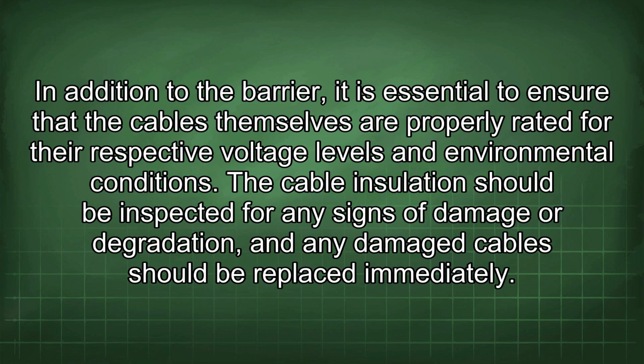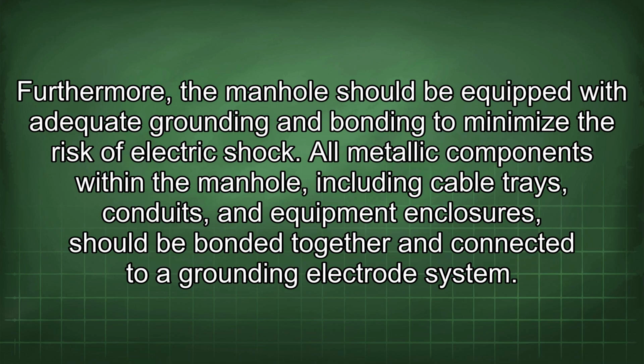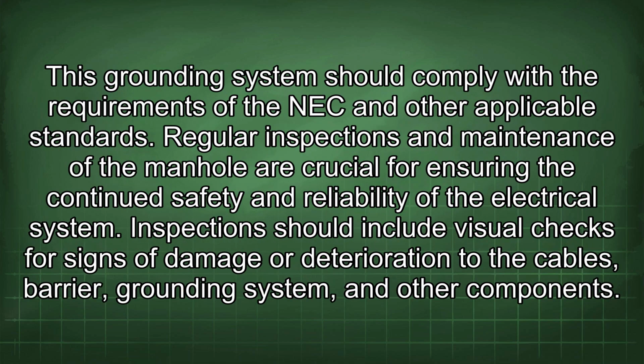In addition to the barrier, it is essential to ensure that the cables themselves are properly rated for their respective voltage levels and environmental conditions. The cable insulation should be inspected for any signs of damage or degradation, and any damaged cable should be replaced immediately. Furthermore, the manhole should be equipped with adequate grounding and bonding to minimize the risk of electric shock. All metallic components within the manhole, including cable trays, conduits, and equipment enclosures, should be bonded together and connected to a grounding electrode system. This grounding system should comply with the requirements of the NEC and other applicable standards. Regular inspections and maintenance of the manhole are crucial for ensuring the continued safety and reliability of the electrical system.